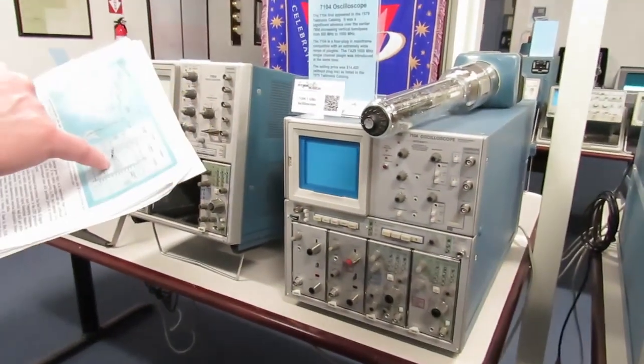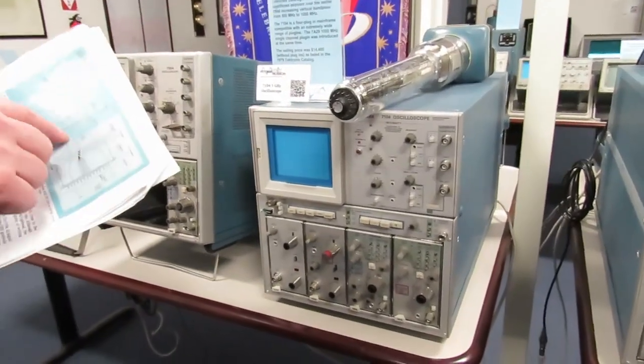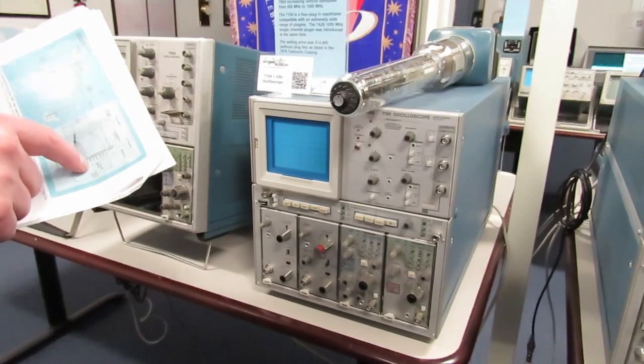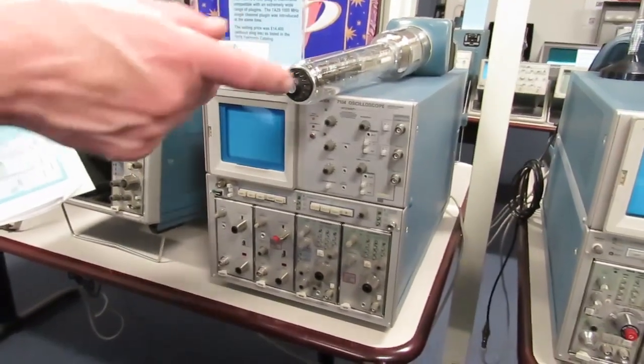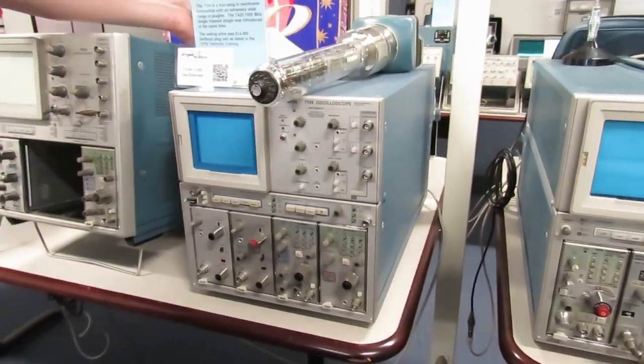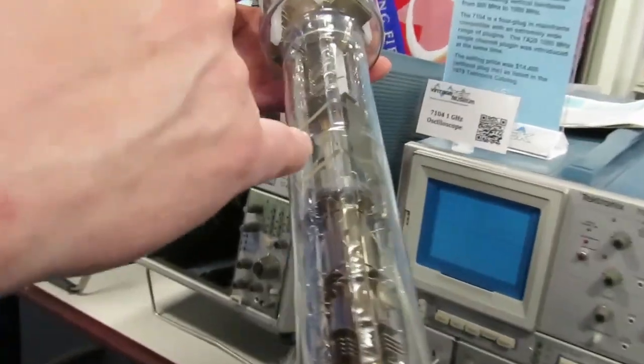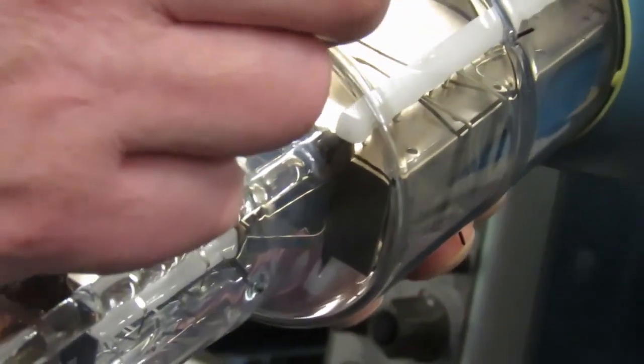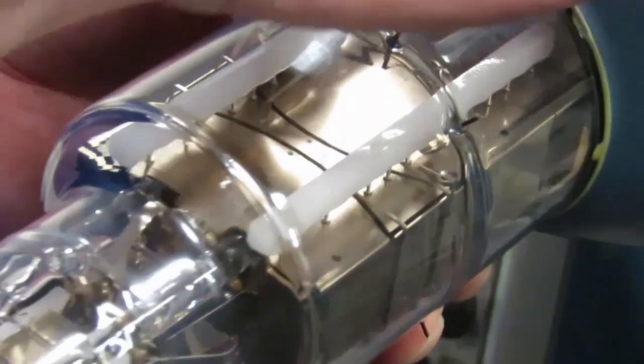It's like photomultiplier tubes, which have multiple dynodes, where the electrons bounce off and through secondary emission are amplified. Because of that very high intensity, effectively, from the microchannel plate amplification, this can do one-shot, nanosecond type things, like the one in the front. But the plates are distributed; there's actually a transmission line. The signal goes down here. As the electron beam moves, the signal goes down with it, so that you get much better deflection sensitivity. This also has distributed horizontal plates because of the high-speed sweep. And then it has these lenses that magnify the image so that you get better sensitivity.